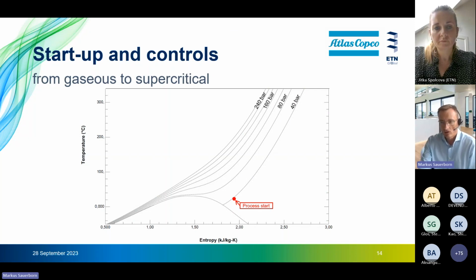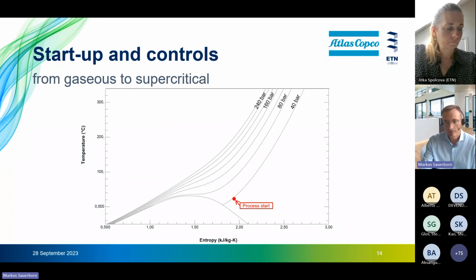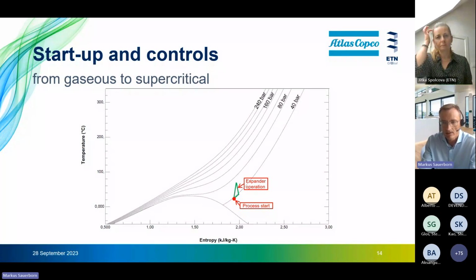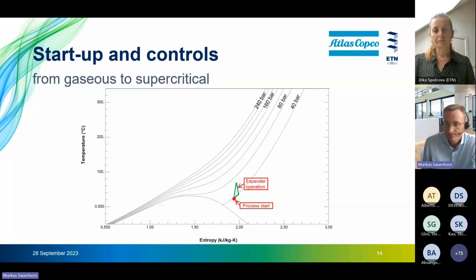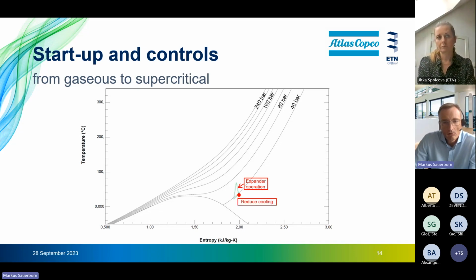Now the startup procedure is shown in the TS diagram. The red dot here represents the compressor suction conditions. We will see that in the animation. In the following animation, the process loop operating cycle and its shift during startup sequence will now be shown marked in green like this. Now, after starting the machine, the compressor inlet temperature was increased up to 35 C by reducing the cooling power. This means above the critical temperature. Next, the heat load from the primary heat source is increased up to 100 degrees C expander inlet temperature, and now the loop and the expander operating conditions shift in the TS diagram like this. You see, we reduce the cooling, we increase the heat load, the loop shifts like this.